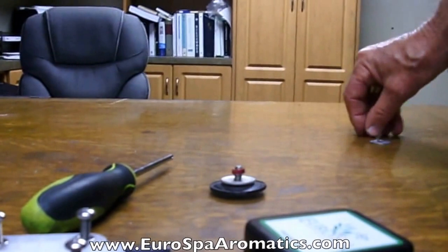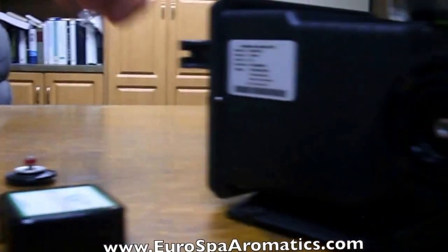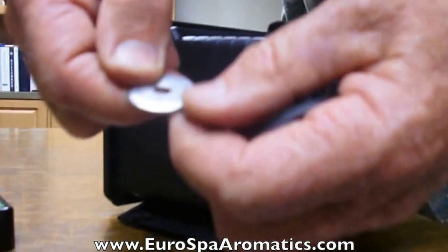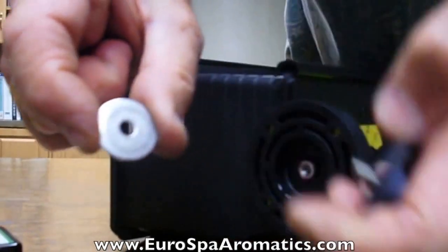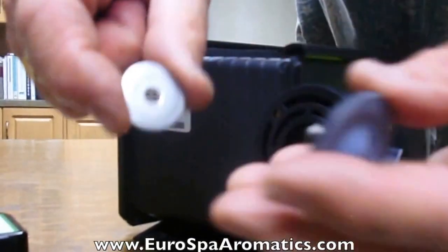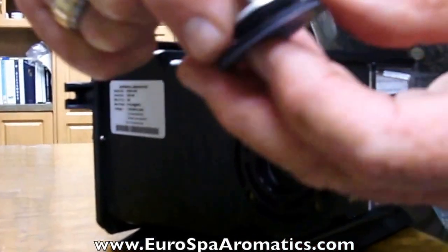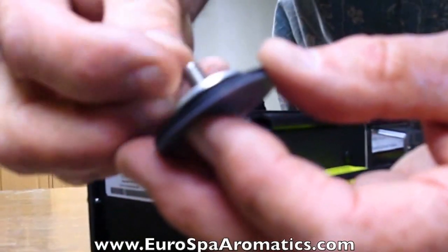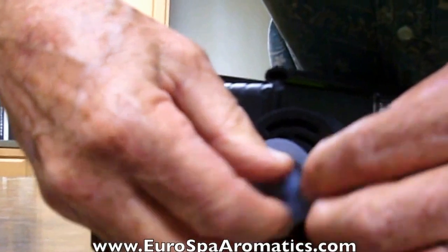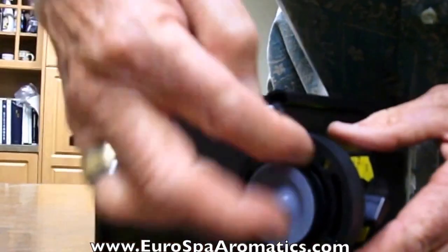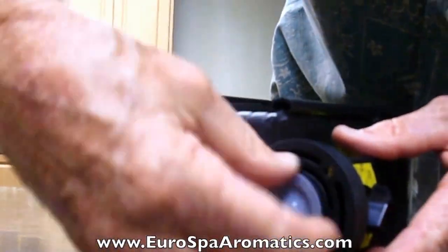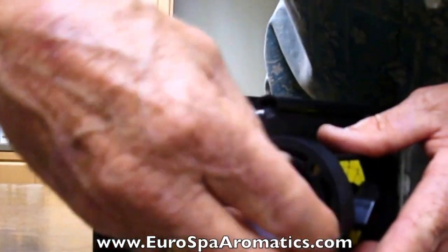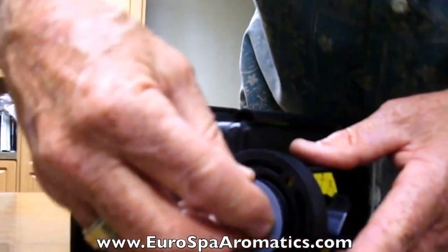When you get your new diaphragm in, it generally comes in 3 parts. And you'll notice that on this washer behind the pump head, it says the diaphragm side. Be sure that goes next to the diaphragm. The spacer ring goes after that, and it simply threads right back in a clockwise position. Again, you don't need to pull it up real tight. Usually just finger tight is enough.